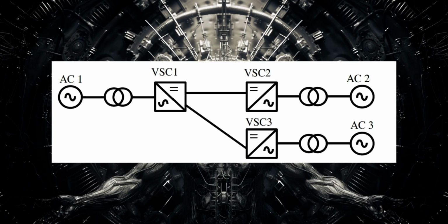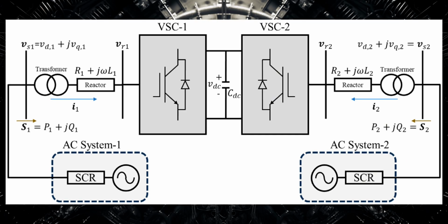Multi-terminal HVDC, MTDC, connects more than two converter stations, enabling power flow between multiple locations. It is used for offshore wind integration, grid interconnections, and meshed HVDC networks, but requires advanced control strategies. Back-to-back HVDC is a system where two converters are directly connected without a transmission line, allowing asynchronous AC grids to exchange power. It is often used for grid stabilization, frequency control, and interconnecting different power systems.